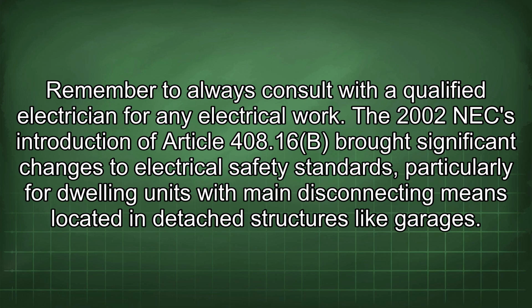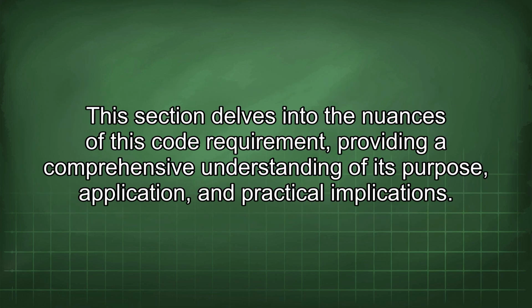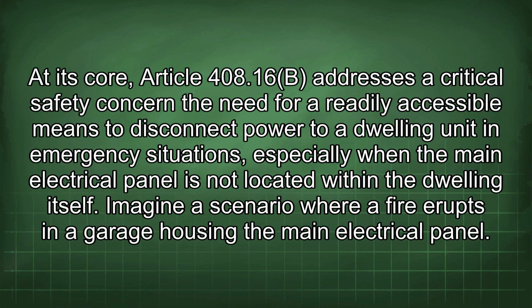The 2002 NEC introduction of Article 408.16(B) brought significant changes to electrical safety standards, particularly for dwelling units with main disconnecting means located in detached structures like garages. This section delves into the nuances of this code requirement, providing a comprehensive understanding of its purpose, application, and practical implications. At its core, Article 408.16(B) addresses a critical safety concern: the need for a readily accessible means to disconnect power to a dwelling unit in emergency situations, especially when the main electrical panel is not located within the dwelling itself.